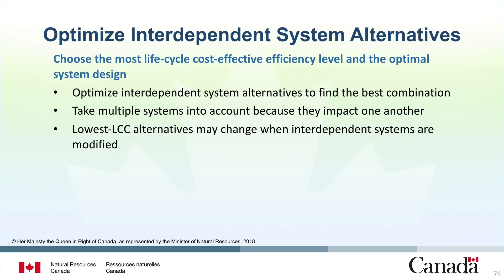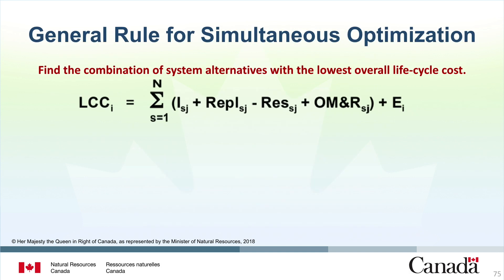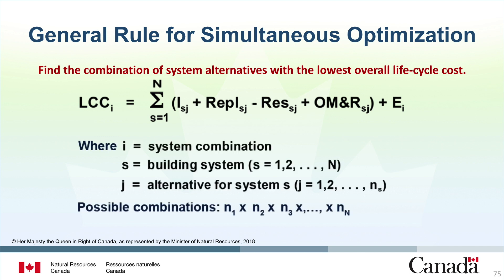Whether evaluating a single system independently or several interdependent systems simultaneously, the general rule for simultaneous optimization is the same: find the design alternative and performance level with the lowest lifecycle cost. Good examples include level of insulation to be installed in a roof, wall, or floor, level of thermal performance for window systems, efficiency of a furnace or boiler, energy efficiency ratio or SEER for an air conditioner or heat pump system, and collector area of a solar heating system. Since a facility has multiple systems that affect each other, it is important to account for these interactions. In many cases, the lowest LCC alternatives may change when interdependent systems are modified. For instance, if the building envelope becomes more thermally efficient, the savings from HVAC system improvements will diminish, and vice versa.